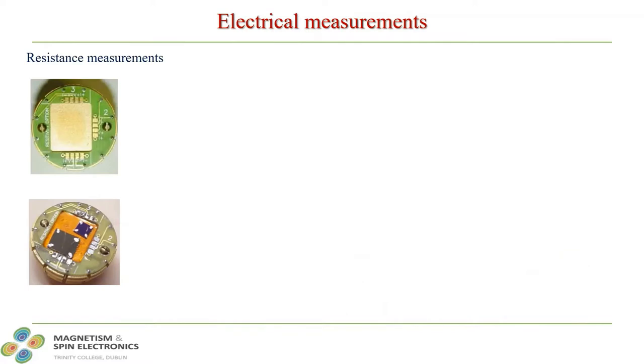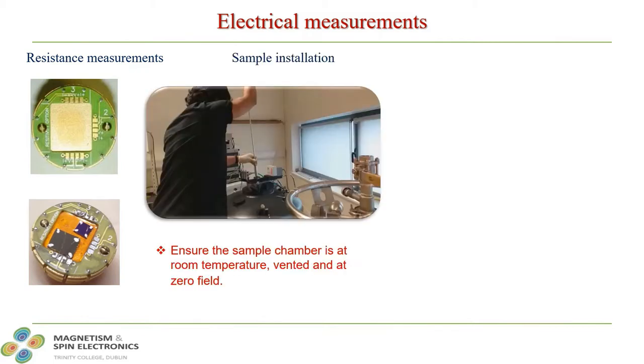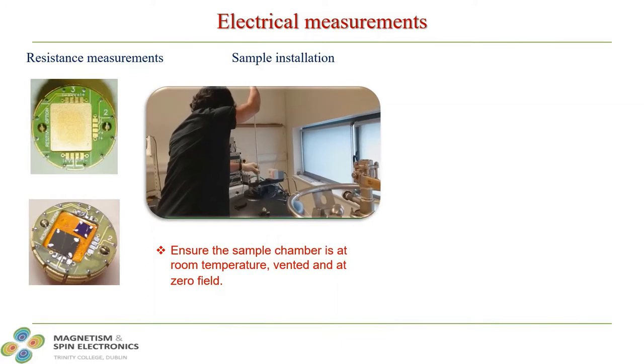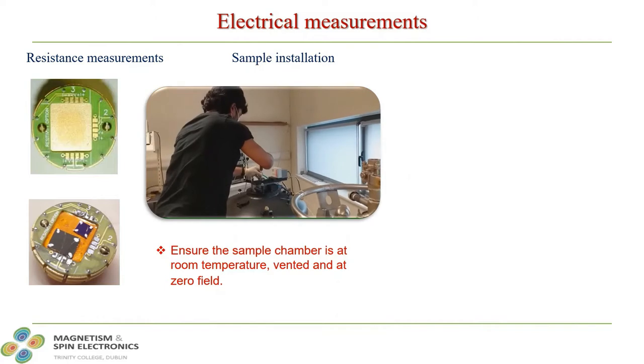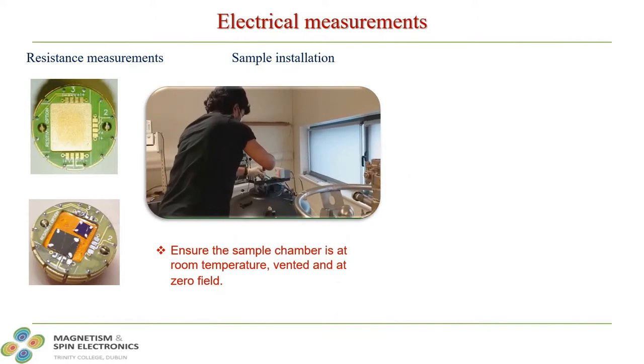First, the electrical measurement. The standard resistance of the sample can be measured by mounting the sample on a 3-channel resistive puck. It allows us to measure 3 samples simultaneously. As shown below, 2 samples have been configured to simultaneously measure the anomalous Hall effect in the thin film sample.